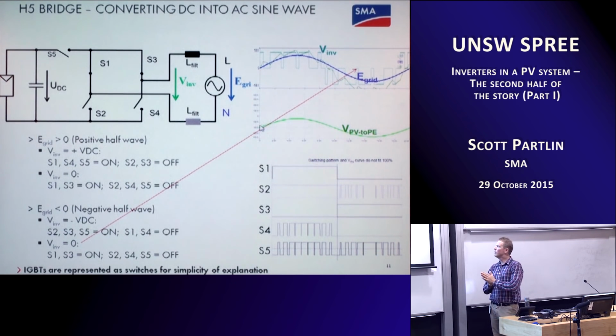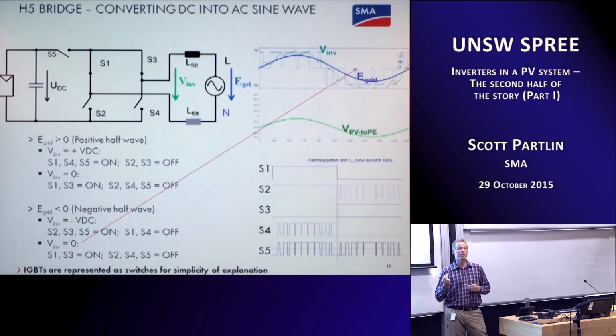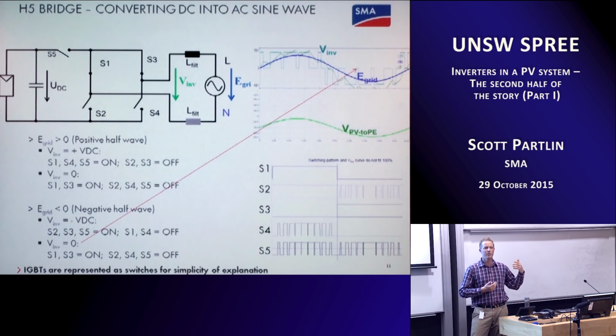The other thing to note is that with a transformerless inverter, there's two types of inverters, and I'll talk about this a little bit later, but a transformerless inverter means that there is no electrical separation between the DC and the AC. So the DC voltage is tied to the AC, and so as the AC voltage rises and falls, the DC voltage also is forced to rise and fall. Now, that doesn't mean that the DC goes down to 0 volts and no power. All it means is that its reference to Earth changes all the time.